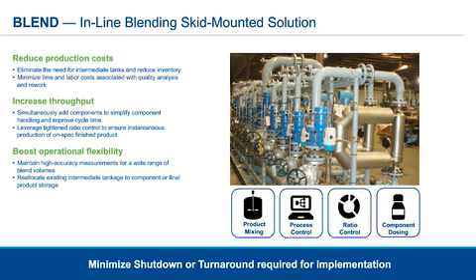For crude blending, where there are flow meters used, many of them are simple uncompensated DP orifice technology, where there is again significant effect when fluid properties change, which is very common with the changing crude slates that we run today. The technology which is most commonly chosen today for optimal performance is the Micro Motion Coriolis meter. The benefits in using this meter for both crude and fuel blending is that they are extremely accurate, have no moving parts, and are independent of changes in the fluid properties.